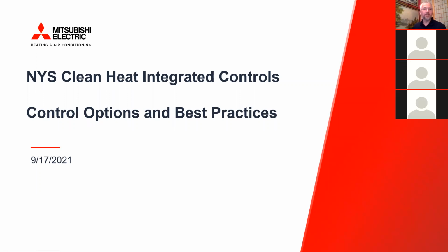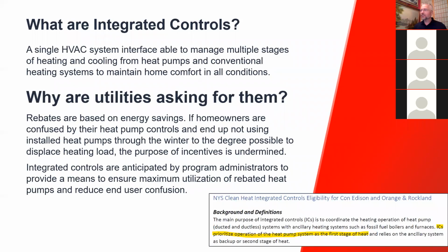Okay, super. Great. So I'm going to dive right into it. So integrated controls, what are we talking about here? Integrated controls is where you have a single point of thermostat control for a consumer, where they're going to be able to adjust the temperature for that zone. If it's the whole house, and it's all ducted, one control point. If it's multiple zones, there are multiple thermostats or control points. But that one control point controls both a primary source of heat and a secondary source of heat.